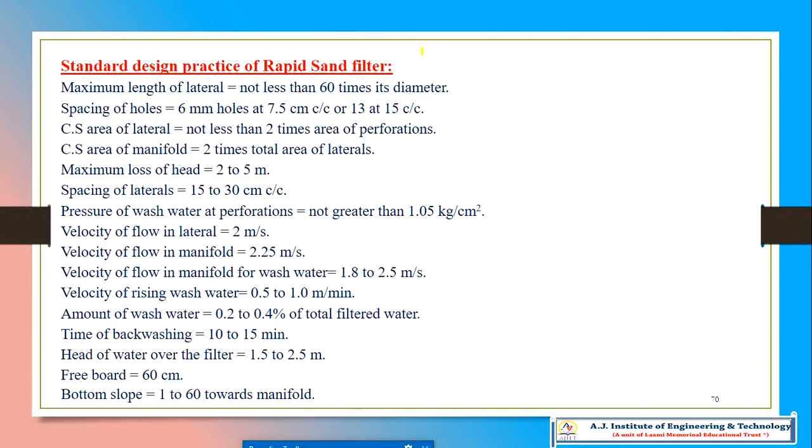Now, as in our case, the maximum length of lateral should be not more than 60 times its diameter. Please remember this very important factor.